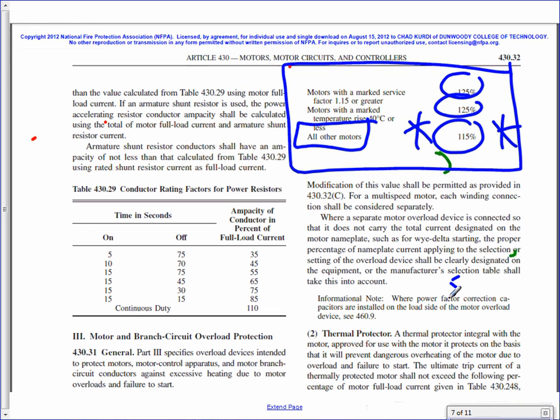There you go, right here. 430.32. 430.32, guys, it tells you the default. Can I start with the default, guys? Because that's important. For overload, the default for all other motors is 115. Your default is what? 115. Unless one of the following: the service factor is 1.15 or greater, then you go 125. The temperature rise is 40 or less, then you go 125.